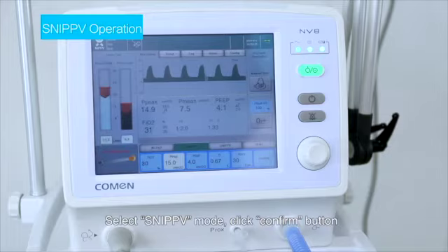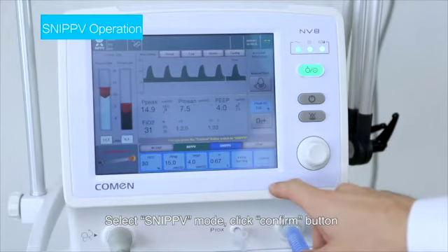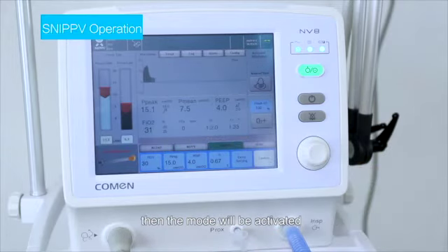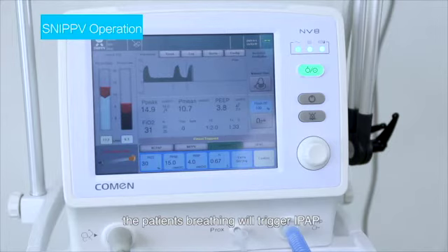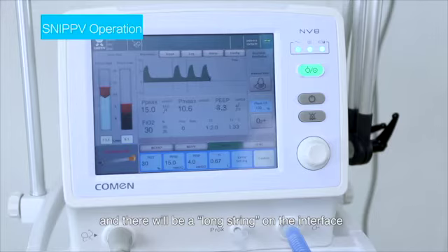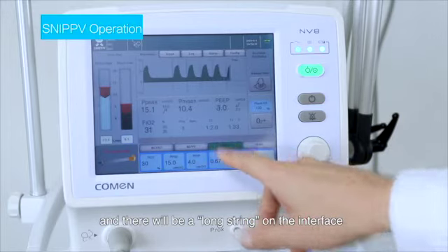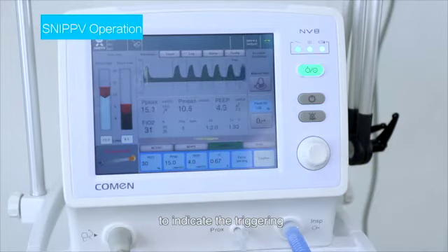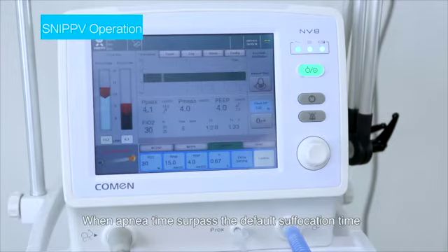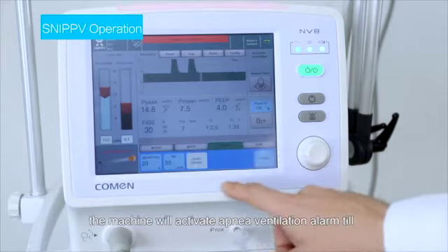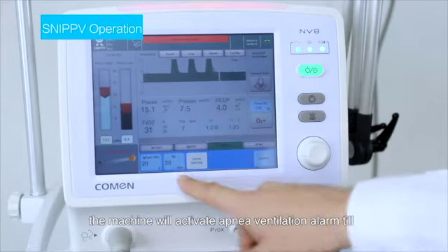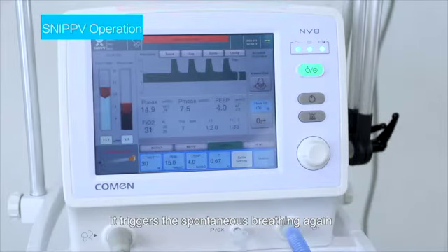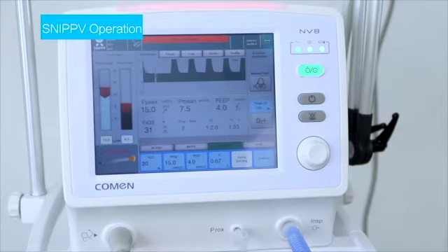SNIPPV mode selection and operation. Select SNIPPV mode. Click Confirm button. Then the mode will be activated. The patient's breathing will trigger IPAP, and there will be a long string on the interface to indicate the triggering. When apnea time surpasses the default suffocation time, the machine will activate apnea ventilation alarm till it triggers the spontaneous breathing again.